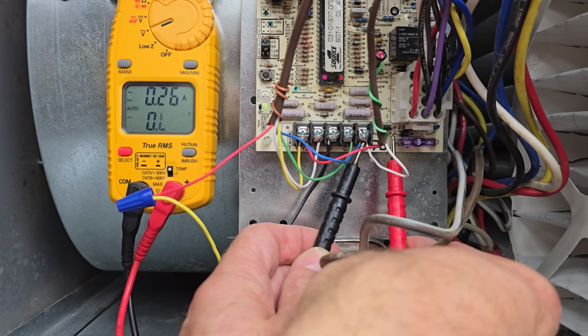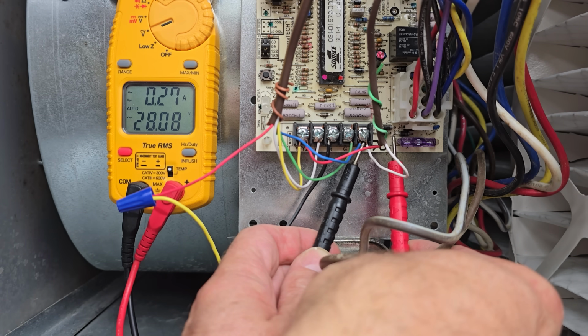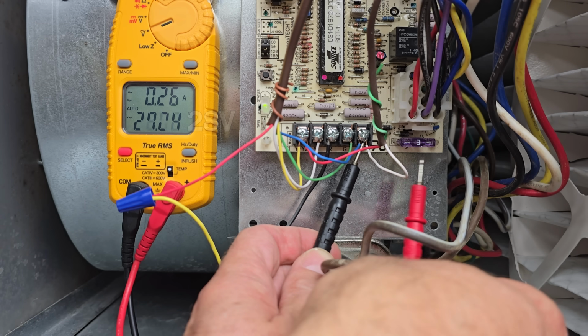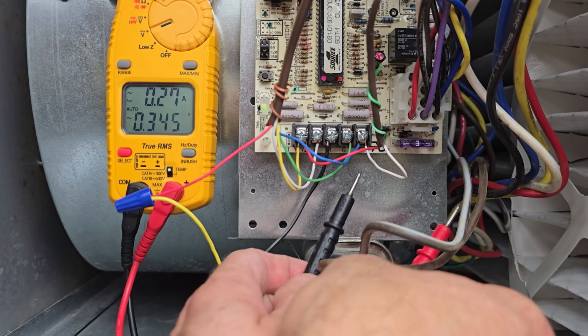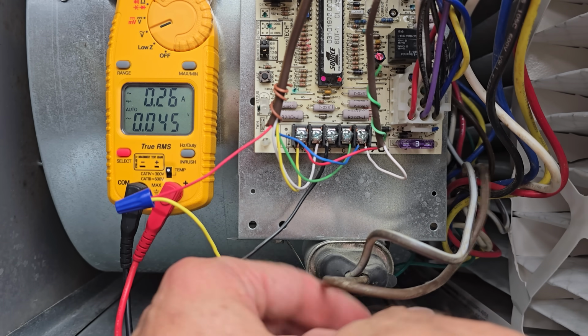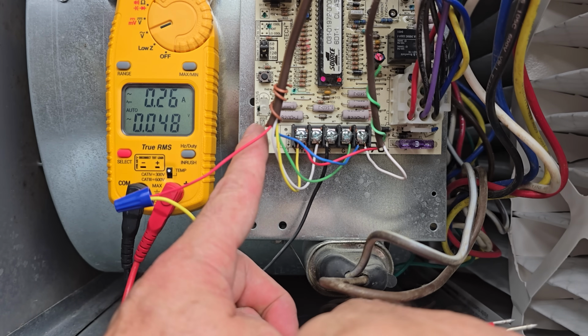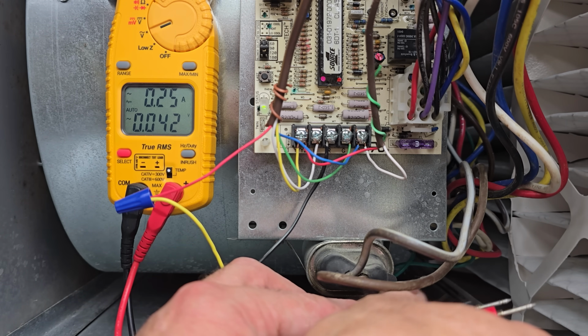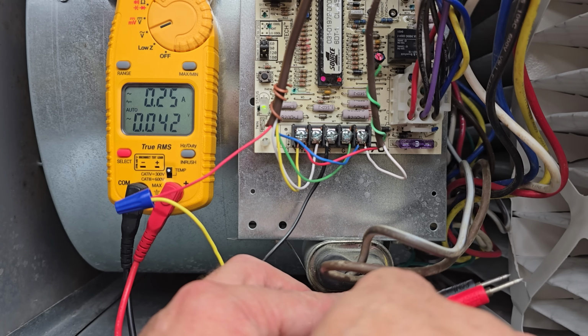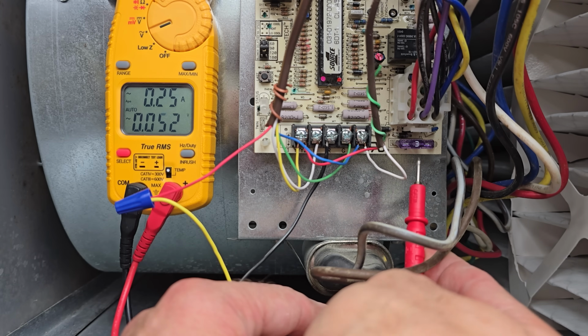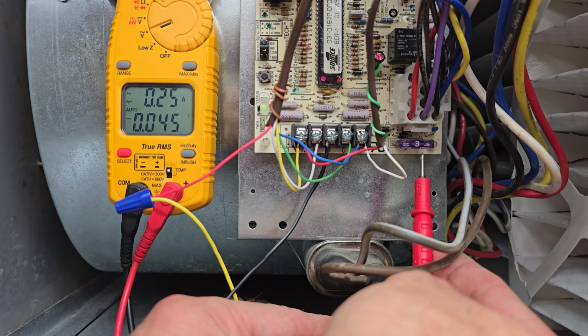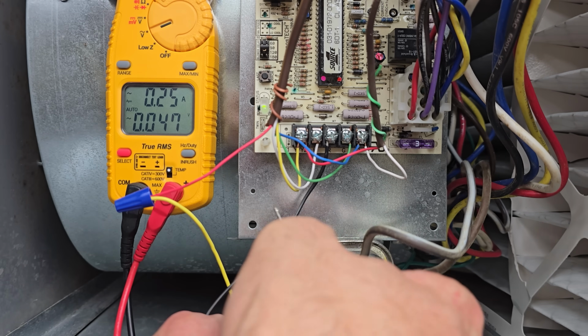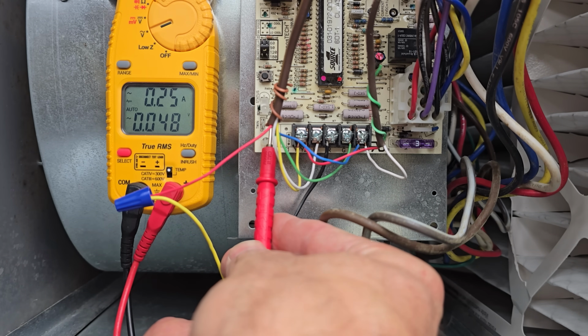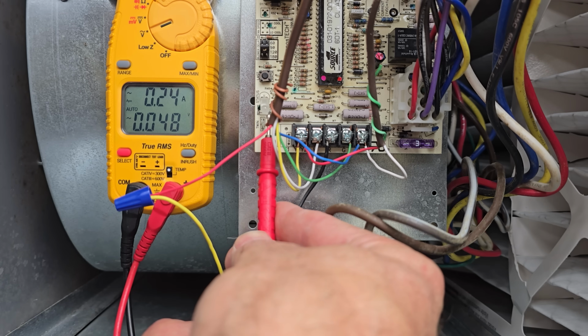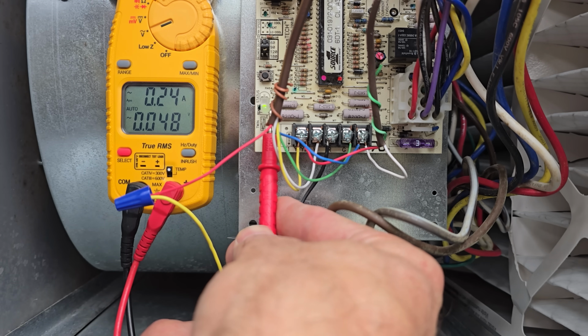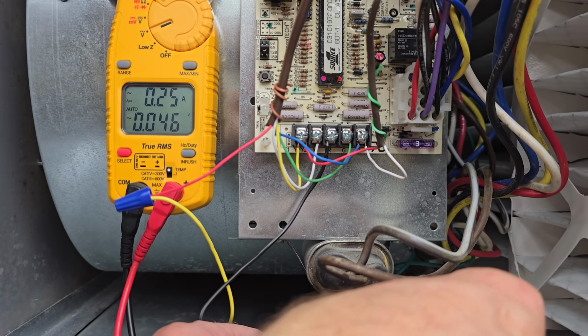Then we would measure over here. And so we're measuring both sides of the fuse. We measure 28 volts, and we know that our fuse is intact because of that. And so if our board still did not have the LED status code light being lit, then it's very likely that the board is the problem. However, there might be some boards where the 24 volt power coming in has to go through some of the safety switches, but that's usually not the case, because when a safety switch trips, like a low voltage 24 volt safety switch that's between, say, 24 and 29.5 volts, what happens is this status light right here is going to blink a specific code when one of those switches is tripped.